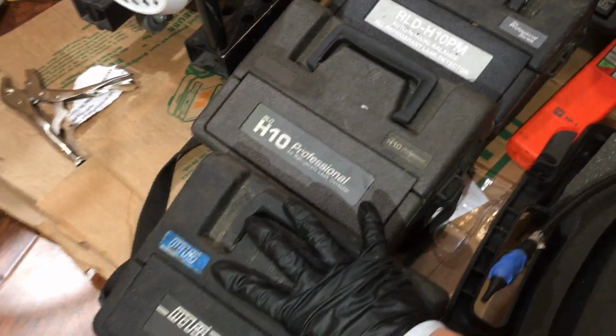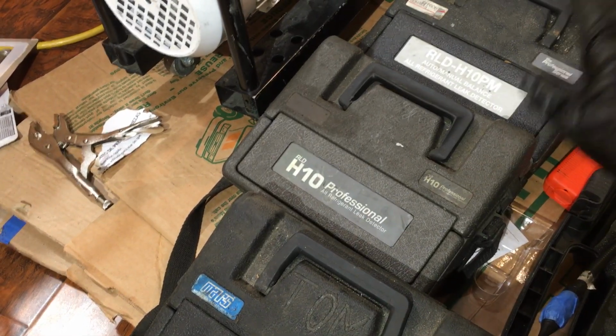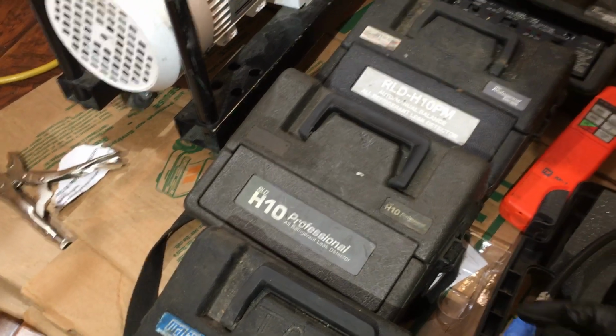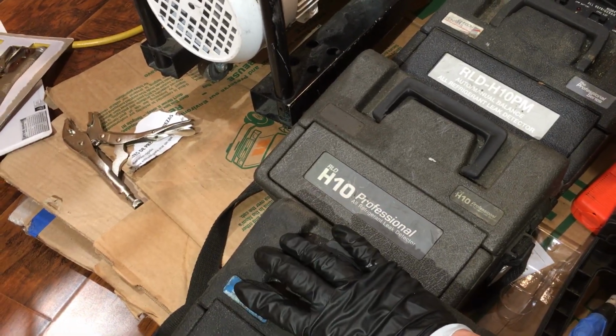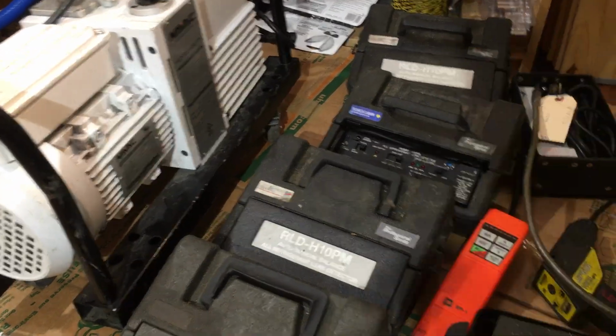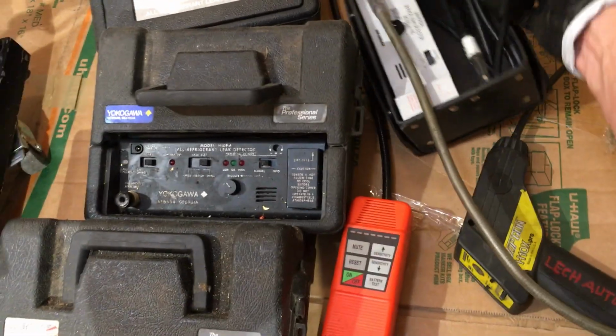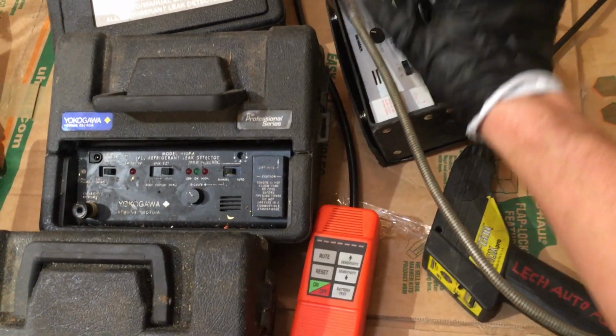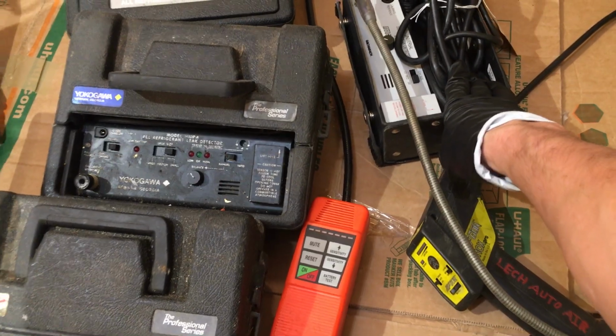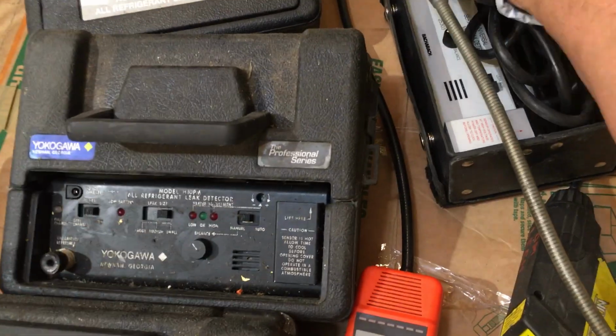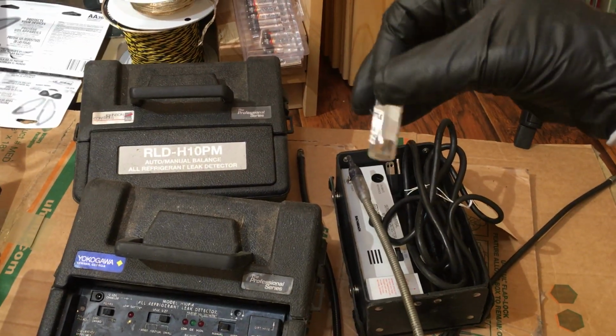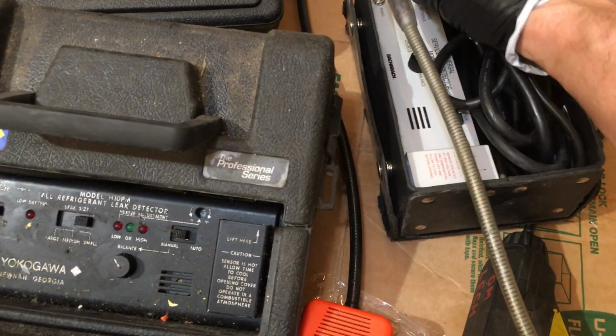These always fail. These are H10s. These have been the best refrigerant analyzer, and sometimes I go through many of them and have to service them at the end of the year. These are anywhere from like $530 to $600 each. And as you see, I have quite a few of them. This is the older style H10 that uses electricity. You have to plug it in the wall. My dad's original one from back in the 70s was $1,500. And these also come with refrigerant leak vials for testing, a calibrated reference bottle. No calibration reference bottle, I don't care who you are, I don't want your product, unless I already have one that I could use your product on.